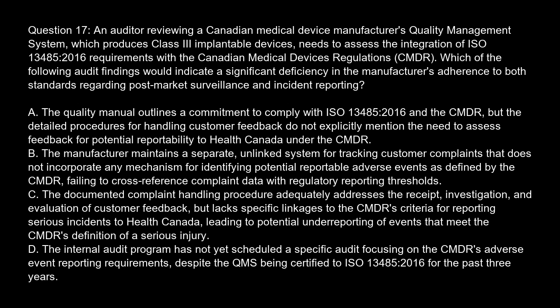The quality manual outlines a commitment to comply with ISO 13485-2016 and the CMDR, but the detailed procedures for handling customer feedback do not explicitly mention the need to assess feedback for potential reportability to Health Canada under the CMDR. Option B. The manufacturer maintains a separate, unlinked system for tracking customer complaints that does not incorporate any mechanism for identifying potential reportable adverse events as defined by the CMDR, failing to cross-reference complaint data with regulatory reporting thresholds.